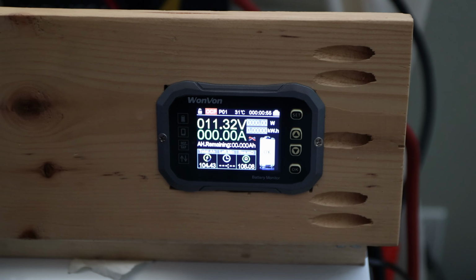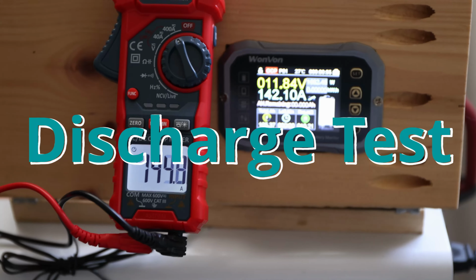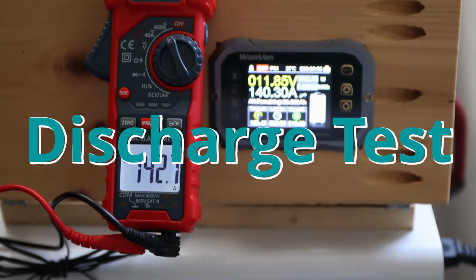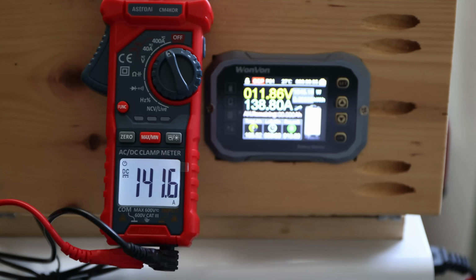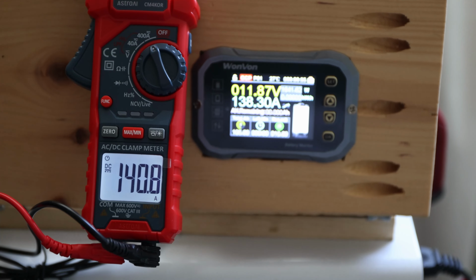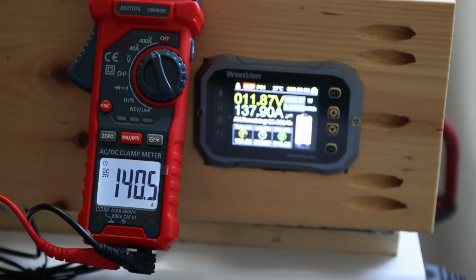Right now we have the high discharge test started, we're at 140 amps. I'll play around a bit and see if we can get even more, because the max continuous discharge current is rated at 100 amp and peak discharge current is 300 amp for less than 5 seconds. Let's see if I can get higher.